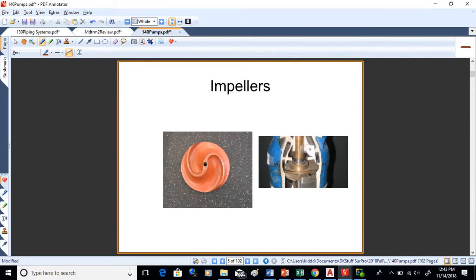The impeller is shaped like a spiral. There are two types of impellers commonly used: open and closed. A closed impeller has little walls on either side and is efficient. Open impellers are less efficient, but you would use them because they don't clog as much. Usually in a wastewater pump you're using an open impeller because things might clog the pump. Closed would be used for clean water.